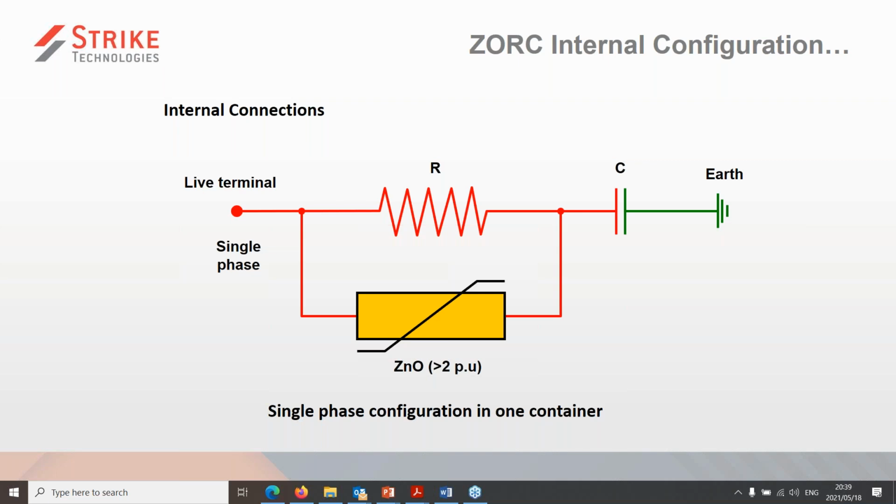The ZNO, or the zinc oxide block, is a gapless nonlinear arrestor with a clamping voltage that is low enough to protect the interturn insulation of those windings. And as we show in our graphic, the ZORC or the MOV would typically activate at a value less than 2 per unit.